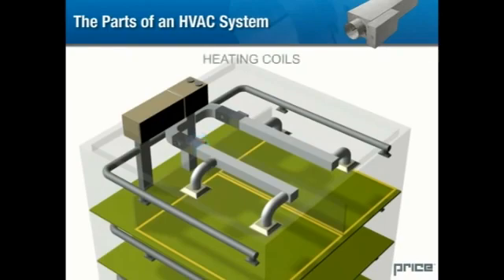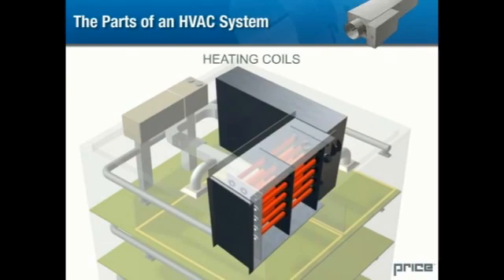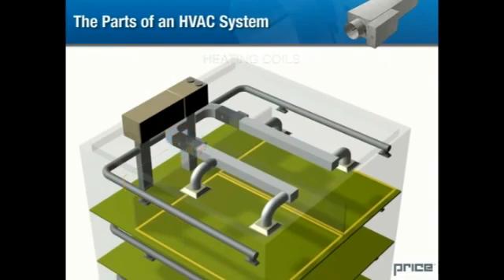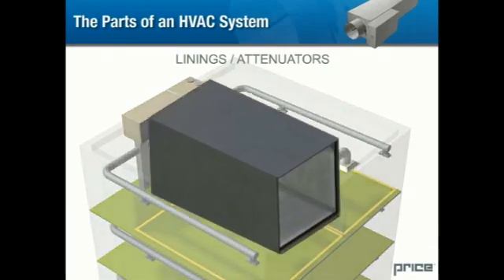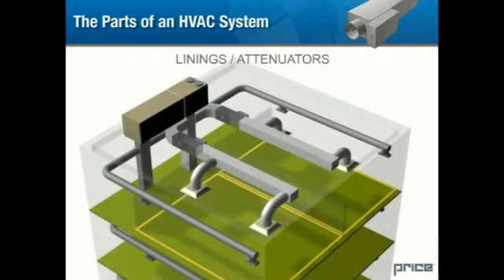Heating coils may be installed after a terminal unit to provide heat on a zone-by-zone basis. Buildings with a high number of occupants may not require extensive heating even during the coldest months of the year. Heating coils offer an efficient way of providing heat for those few areas that require it, and are controlled by the same thermostat system as the terminal unit. Various types of linings are available to dampen noise within a duct. A short length of lined ductwork, called an attenuator, is often installed following the terminal unit to dampen discharge noise.